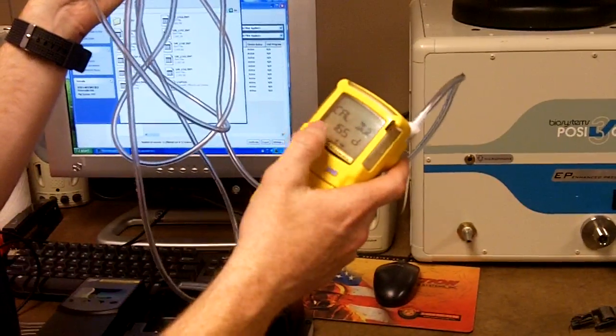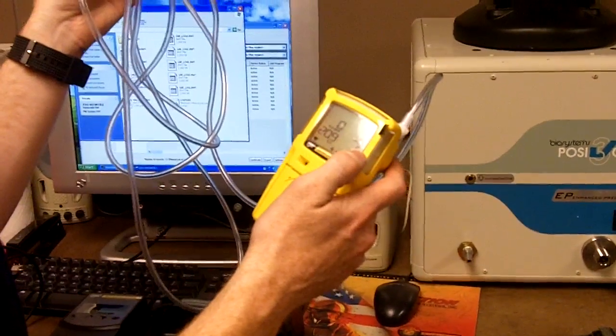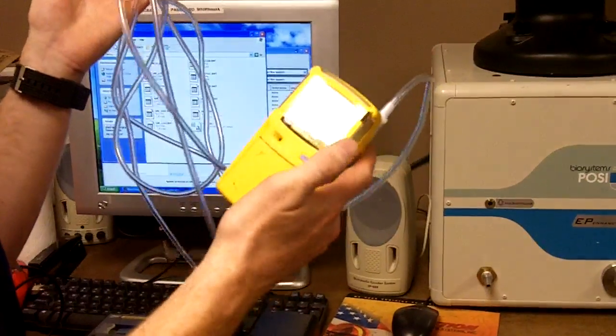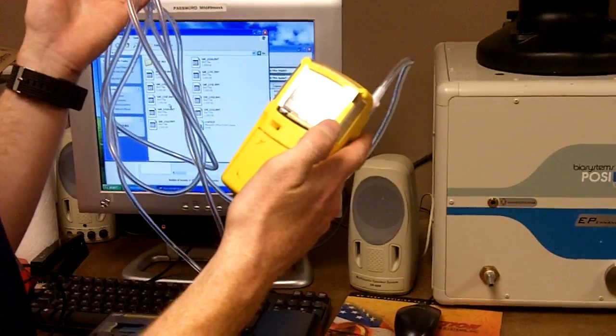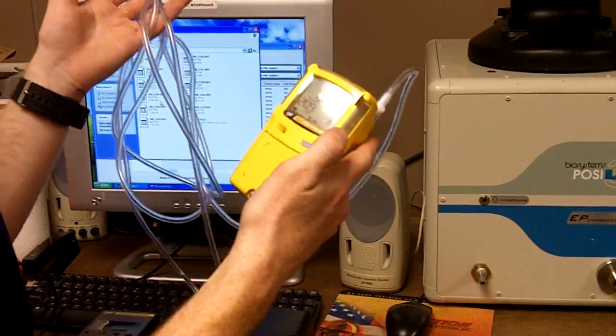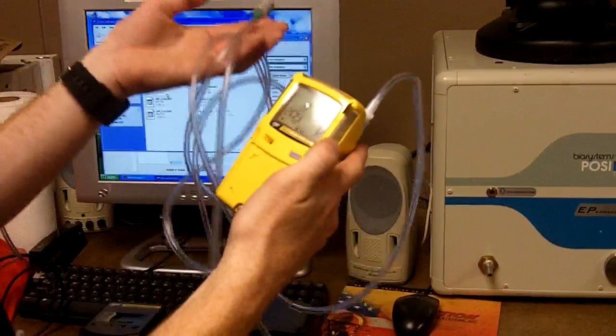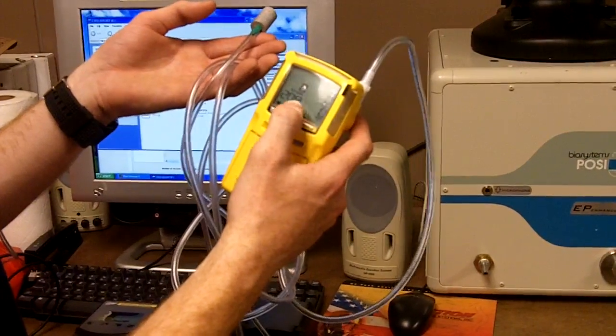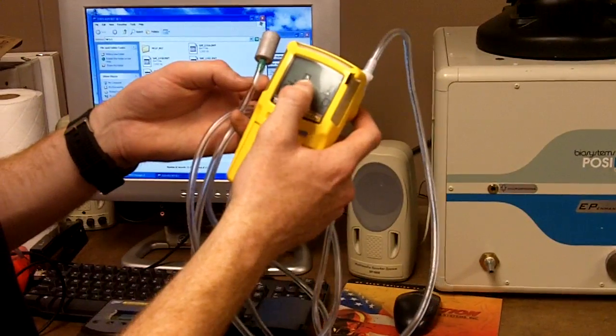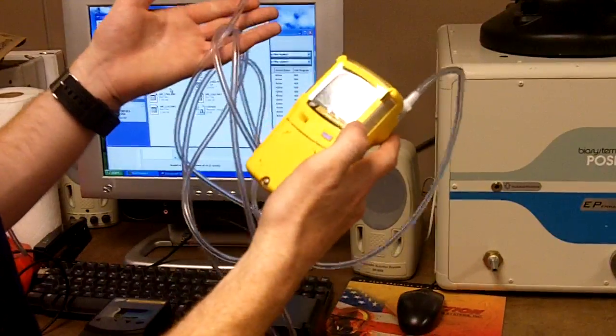It's still going through its calibration. It says calibration due, 165 days left. Again, this by default is 180 days, each calibration needed. So right now it says that it's full of charge. It also has all its checks, and they're good to go.